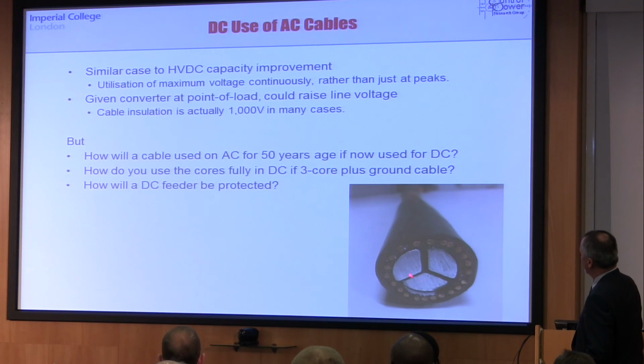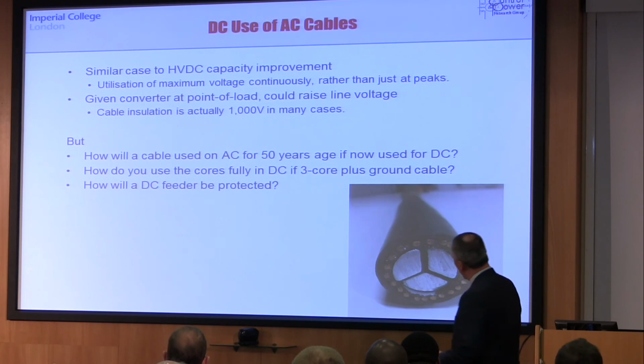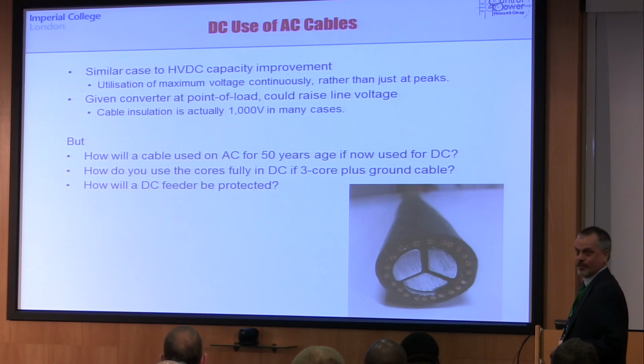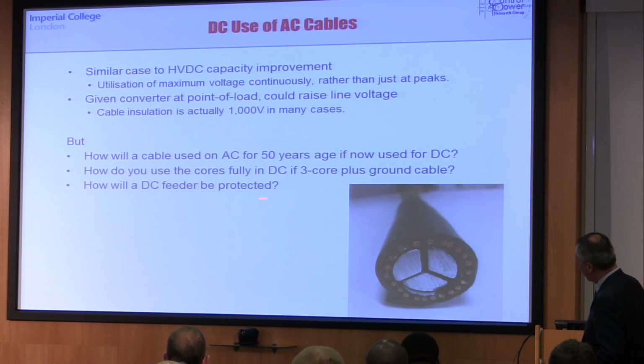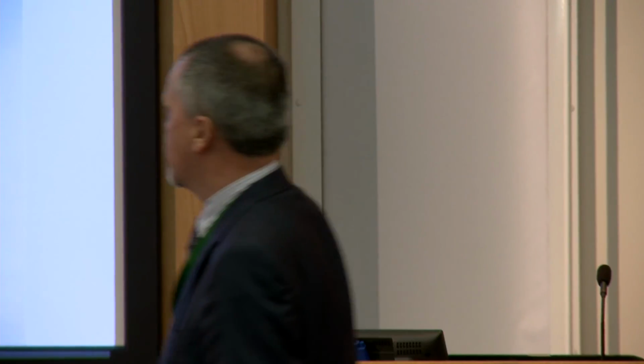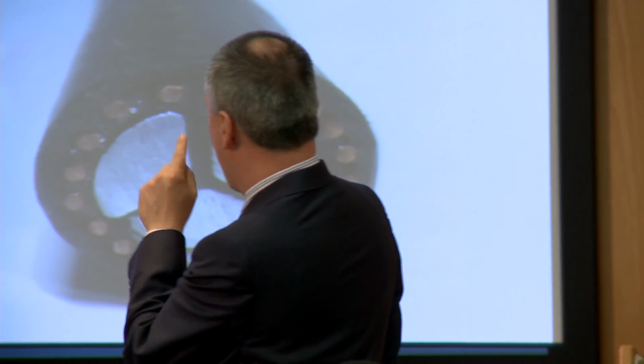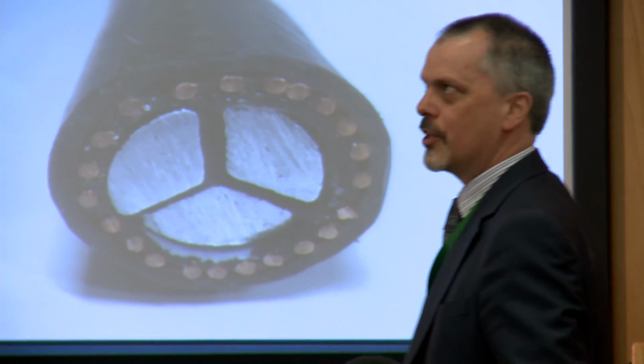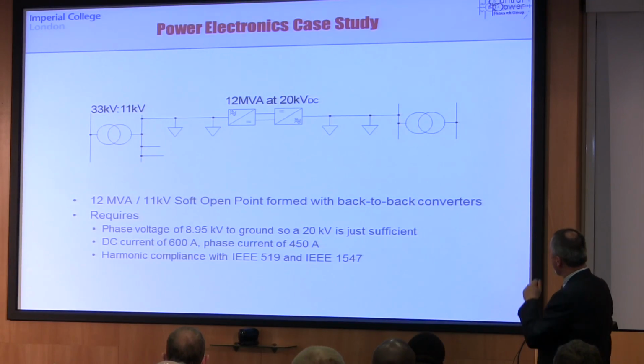If that's a 3-core cable with a combined neutral earth around the outside, then it's not obvious to me how you redeploy those conductors to make effective use on DC. And we have the problem well known in HVDC of how do you protect DC systems. So a lot of innovation, I think, and thinking needed if this solution is going to go somewhere.